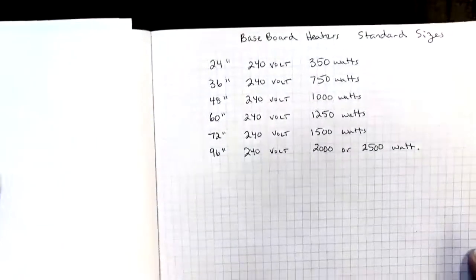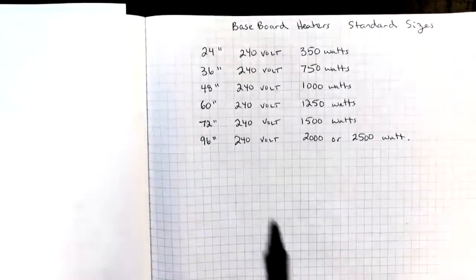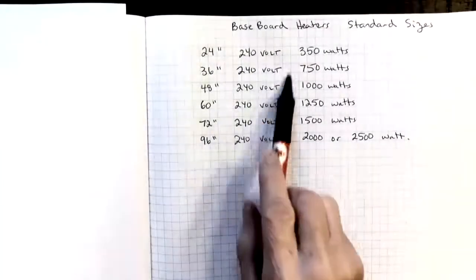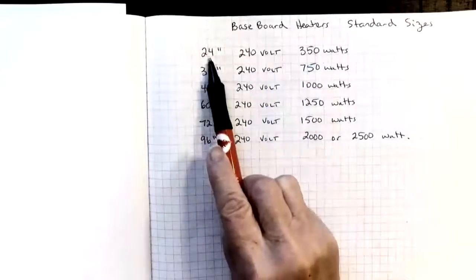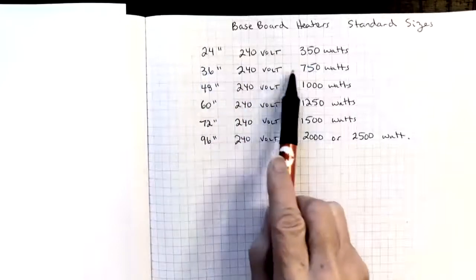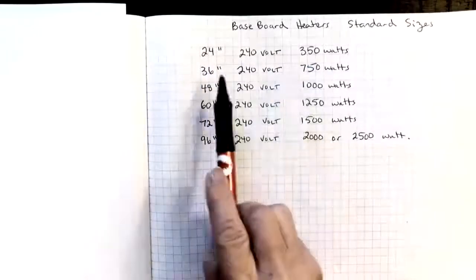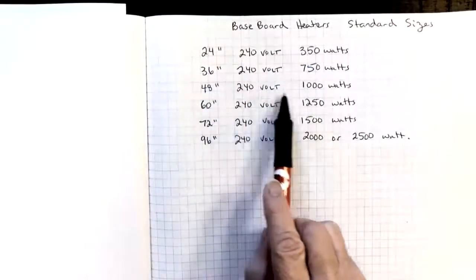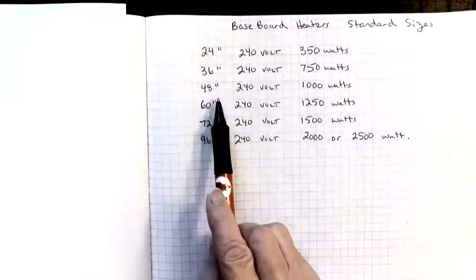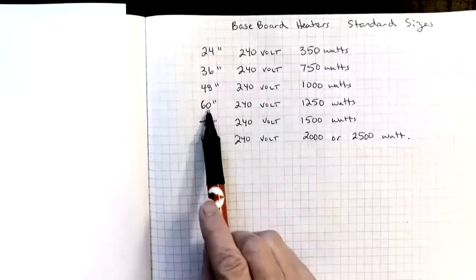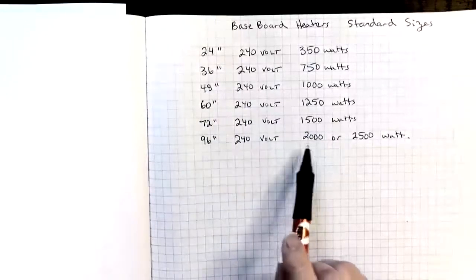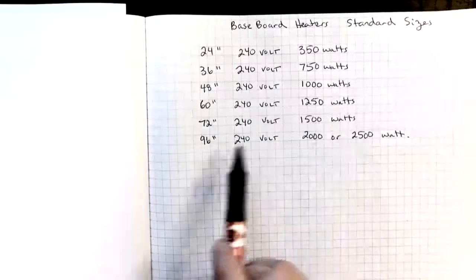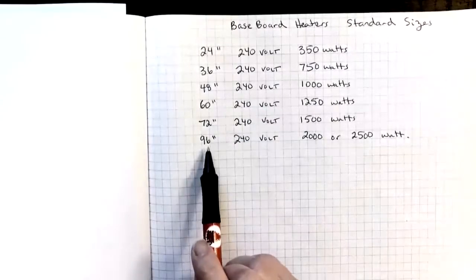First of all, of note is the actual length of baseboard heaters. These are standard sizes and if we look all of these were 240 volts. So a 350 watt baseboard heater typically is 24 inches long. A 750 watt baseboard heater is 36 inches long. 1000 watt is 48 inches long. 1250 is 60 inches long. 1500 is 72 inches long and a 2000 or 2500 watt is 96 inches long.